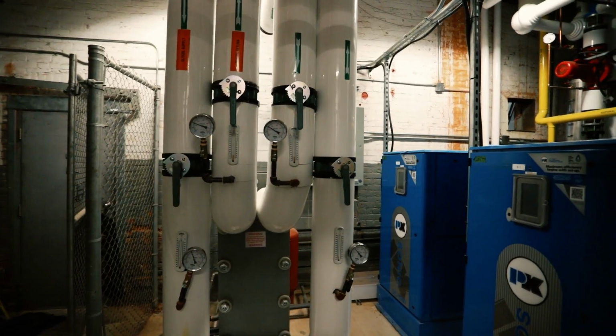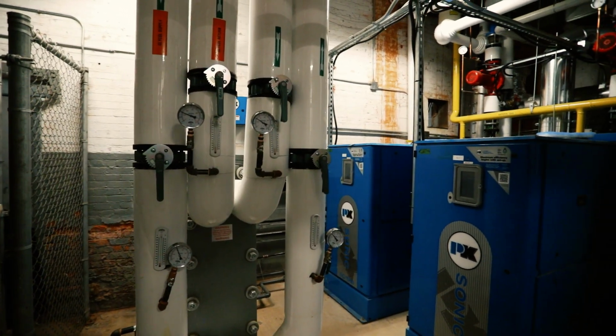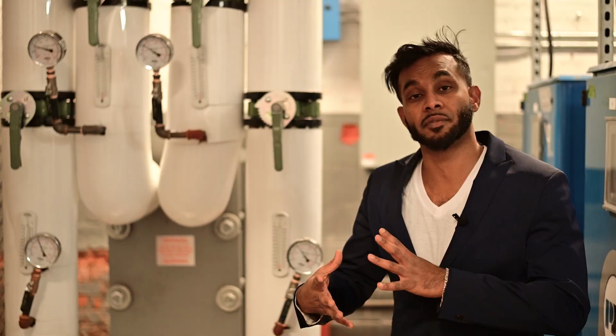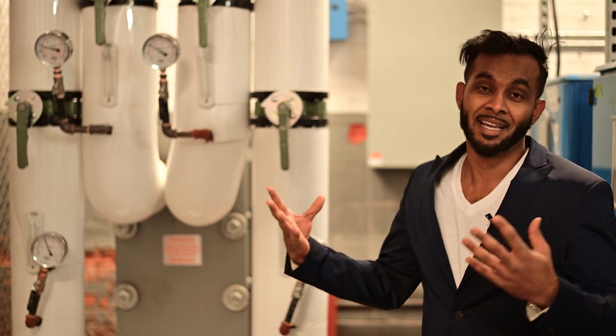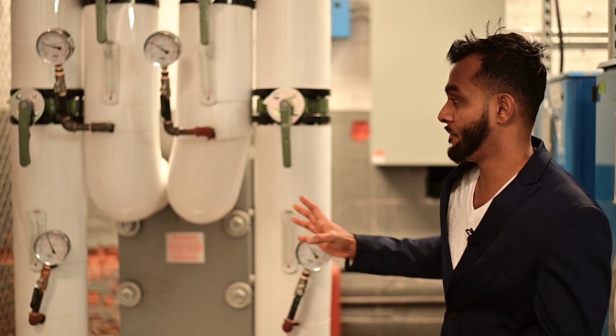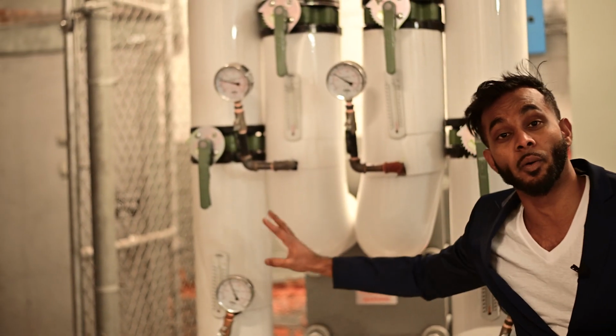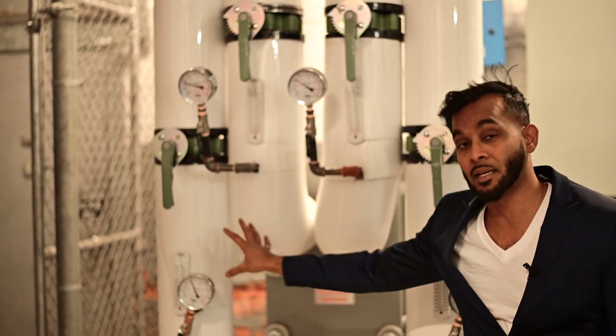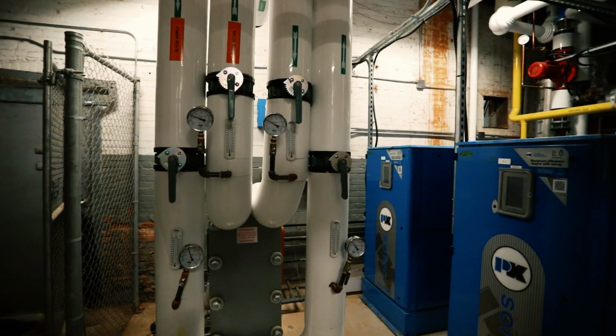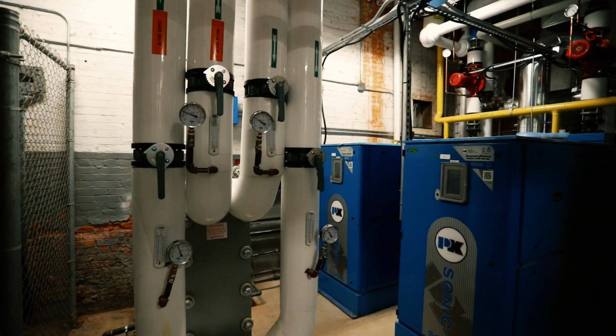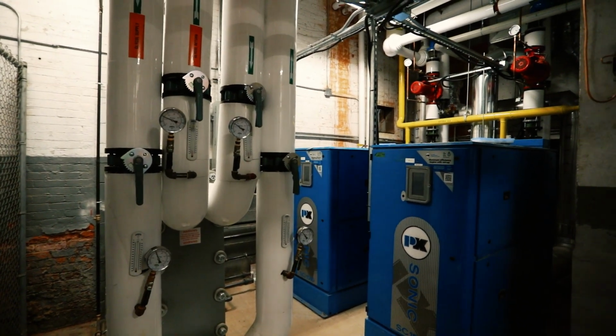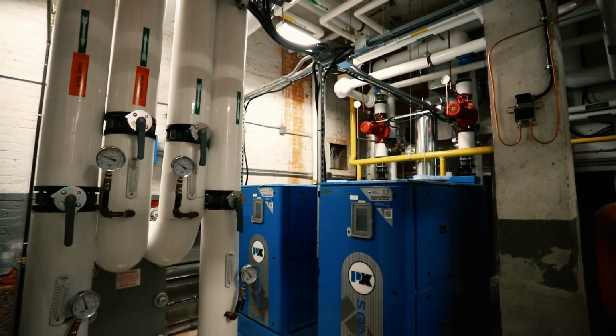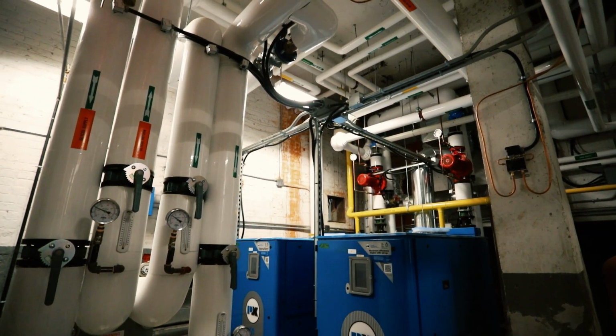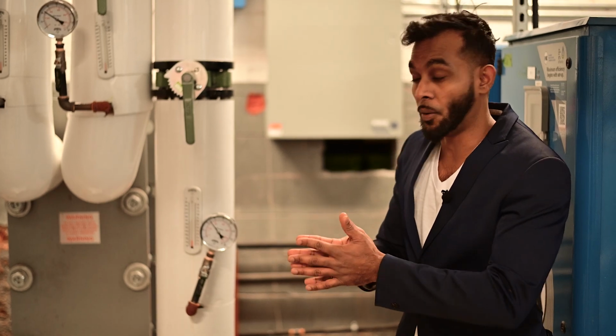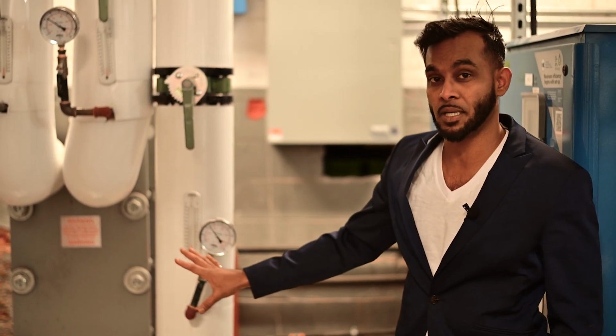What we have here is called a plate heat exchanger. This was a vital component for us to introduce air conditioning into this building. We have these 2 lines going into the cooling tower with glycol, and these two lines going into the building itself. The nice thing about the plate heat exchanger is you never have any mixing of the water, all you have is thermal energy transfer only. That's the nice thing about it, it's called a plate heat exchanger.